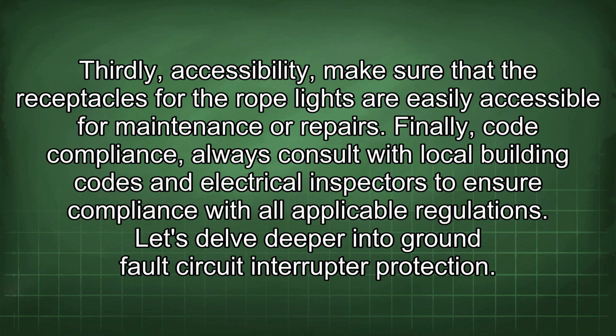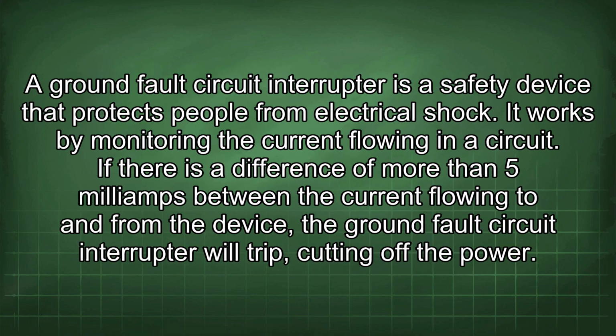Let's delve deeper into ground fault circuit interrupter protection. A ground fault circuit interrupter is a safety device that protects people from electrical shock. It works by monitoring the current flowing in a circuit. If there is a difference of more than 5 mA between the current flowing to and from the device, the ground fault circuit interrupter will trip, cutting off the power.